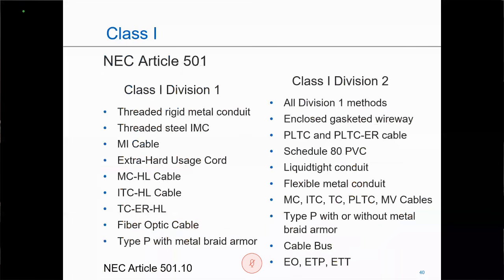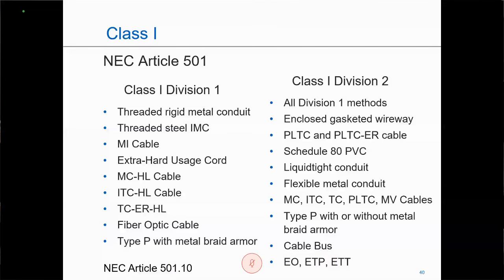Now, when it comes to wiring methods, in Class 1, Division 1, threaded rigid metal conduit. So it can be rigid steel, rigid aluminum, stainless steel, also IMC, MI cable, extra hard usage cord. You know, when we have things such as plugs and receptacles, we need to have some flexibility. So the code says extra hard usage cord. What is extra hard usage cord? Like an SO cord, an S cord. And in fact, a lot of the manufacturers are putting this terminology, extra hard usage, at the top of their catalog pages for those cables that can be used in hazardous location areas.